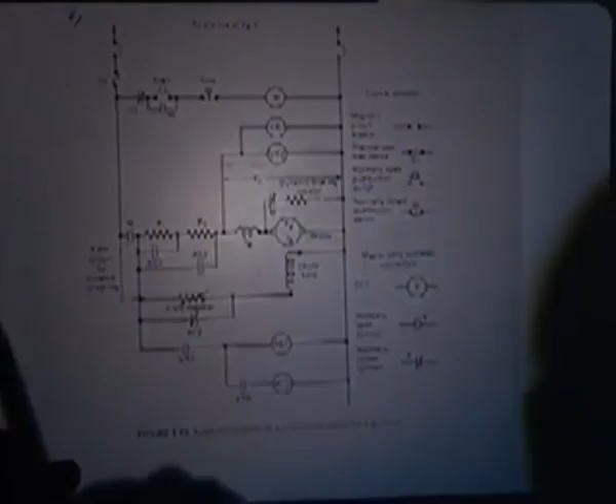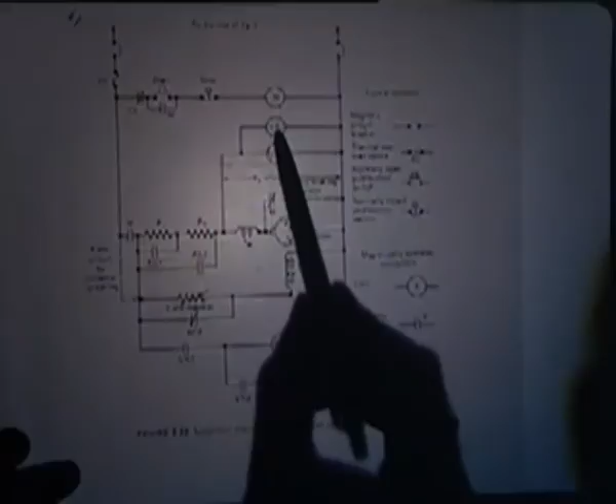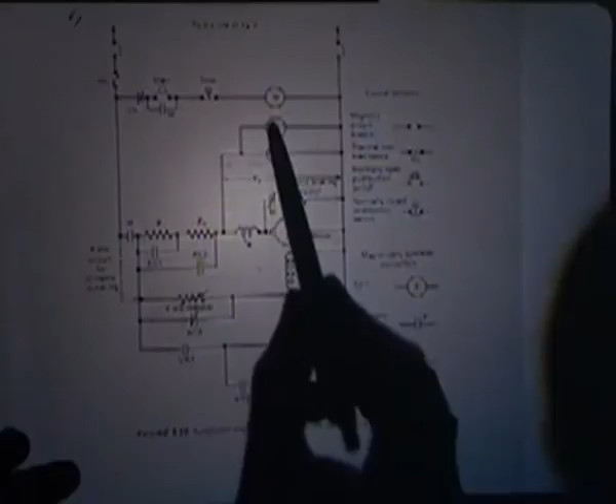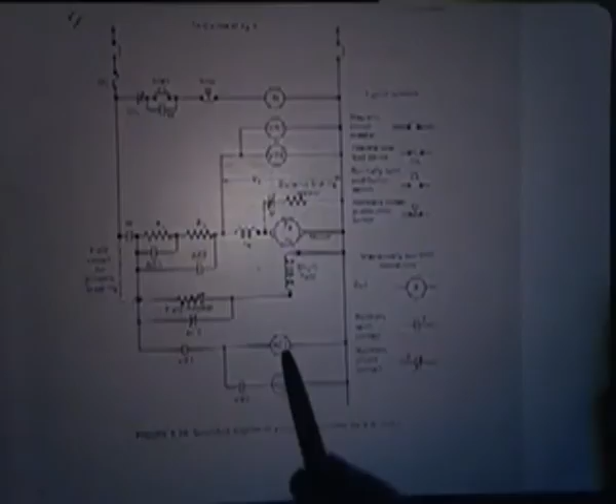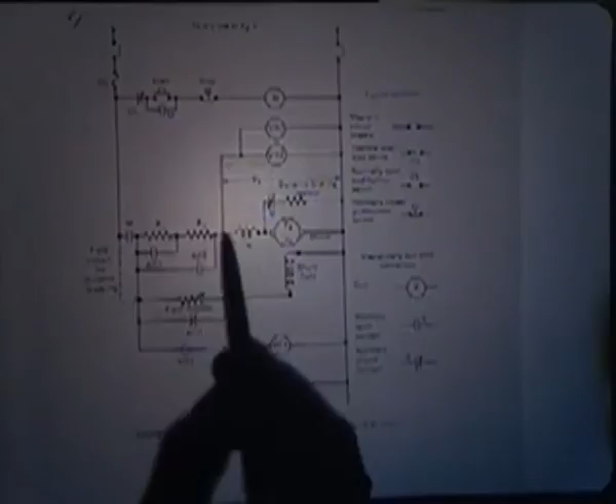Then as you start drawing current and the voltage builds up to a certain value, say VR1, this VR1 coil gets energized. So automatically, as the speed goes up, when the back EMF goes to a certain value, this gets energized. When VR1 gets energized, this VR1 contactor closes. When this contactor closes, the coil AC1 gets energized. When coil AC1 gets energized, the corresponding contactor AC1 closes. When this closes, R1 gets short circuited, so only R2 will now be in the picture.